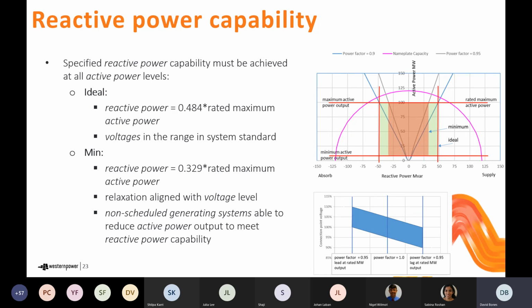The difference between then the ideal and minimum standard primarily relates to how much reactive power needs to be produced. And you can see the dark red vertical bars are identifying the ideal standard, and the lighter red shaded area on the diagram identifying the minimum standard. The ideal standard then requires a reactive power output equal to 0.484 times the rated maximum active power. The minimum, it's 0.329 times the rated maximum active power. And respectively, they're equivalent to achieving a 0.9 and 0.95 power factor at the rated maximum active power output.